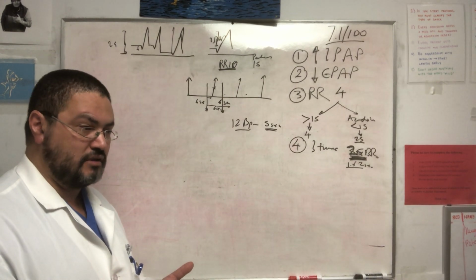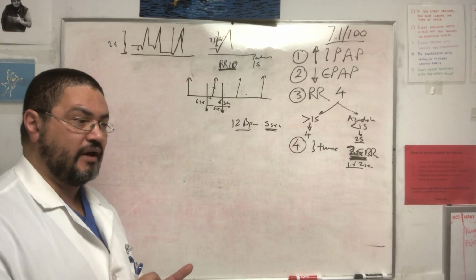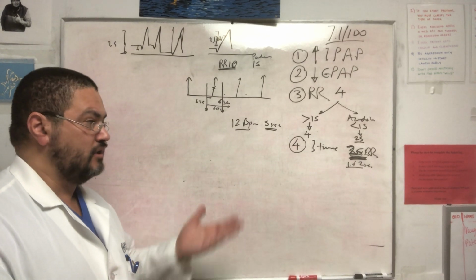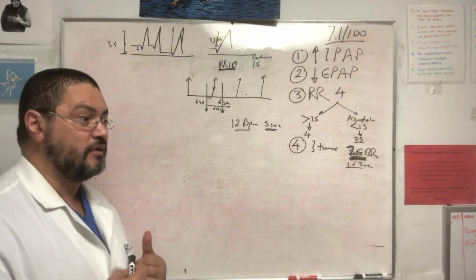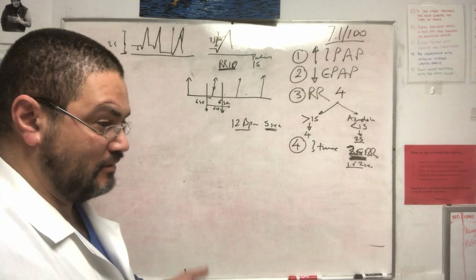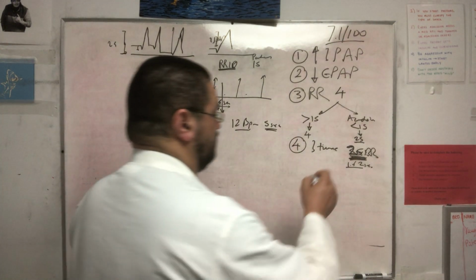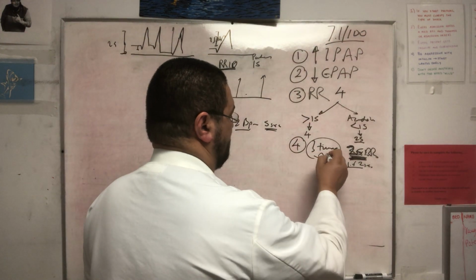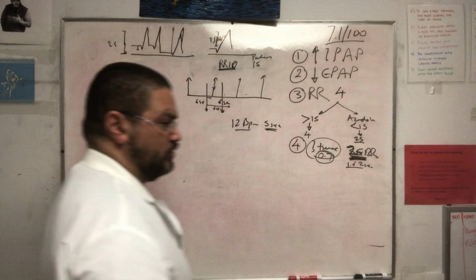If you inverse the I to E ratio, the patient requires more paralysis. Right? So here on the BiPAP, you're inversing the ratio, and somebody was completely awake, not even sedated. It's crazy. So you be careful with the I time. I always set it up at 0.7. There's no need to have I time more than 0.7.